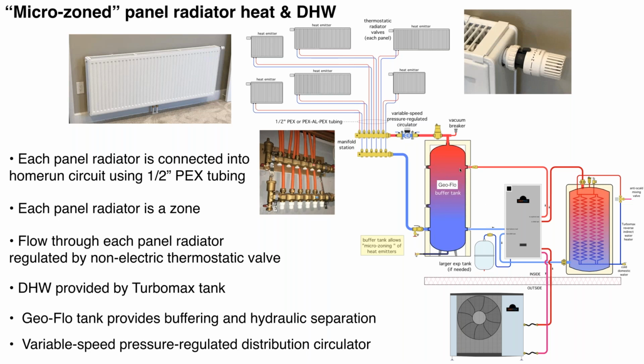We're maintaining our thermal battery. We have quite a bit of thermal mass there. And now each panel radiator simply draws water as necessary. This circulator could be turned on in the fall, and it could be energized 24/7 right through the heating season. And some of you might be thinking, isn't that going to use a lot of electricity if we leave it on? We've actually done some calculations on this, and we find those circulators can run on the order of like 4 or 5 pennies per day, with electric rates at maybe 10 cents a kilowatt hour. This is a very small amount of electricity.